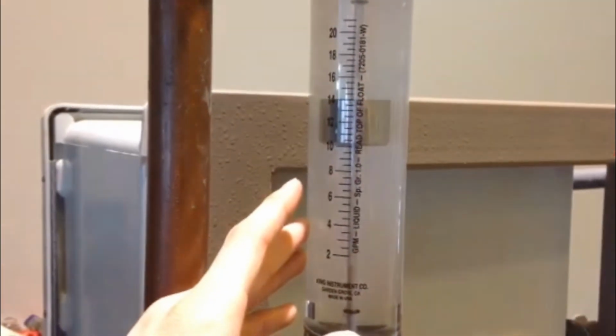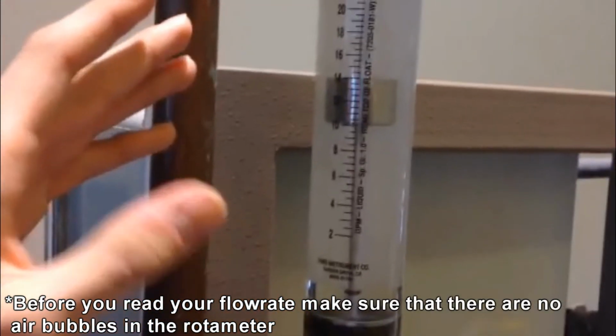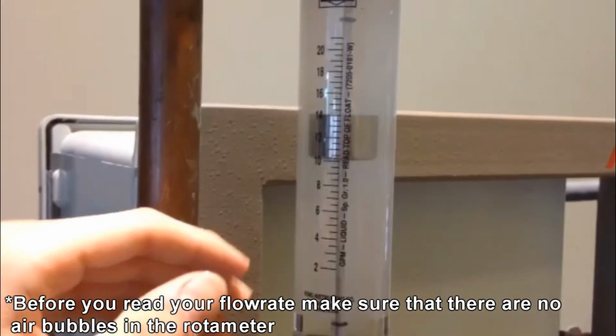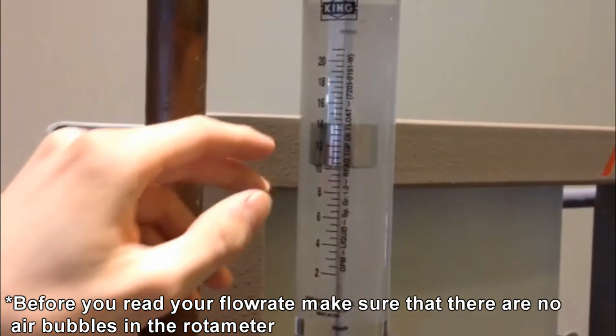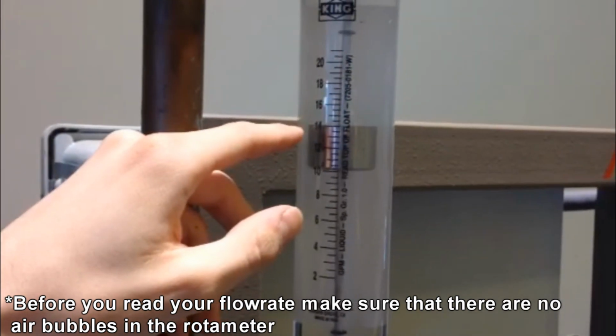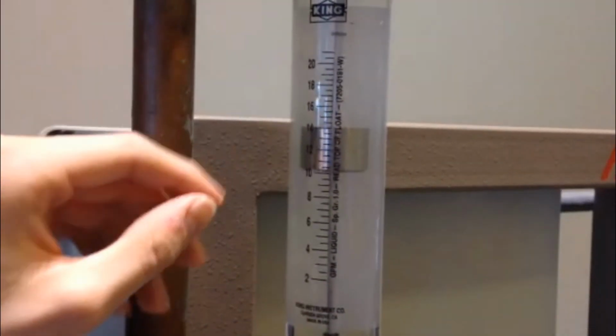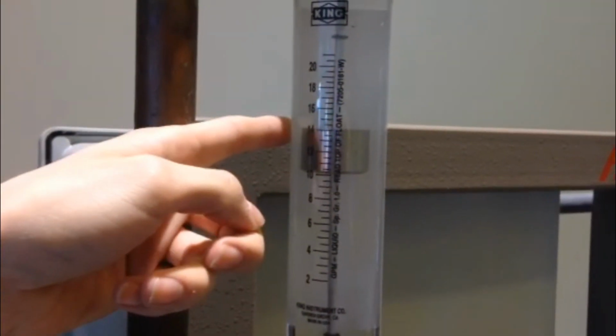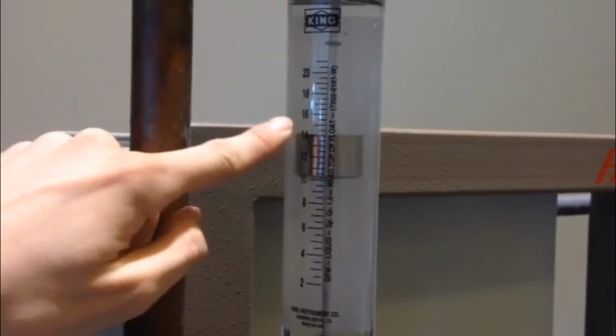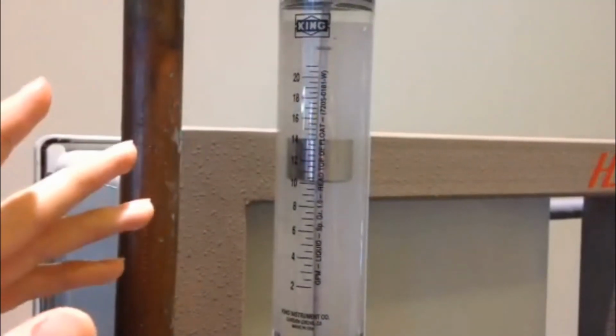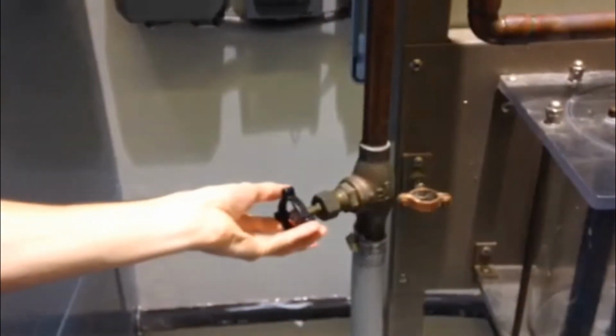So this is a rotameter. It allows us to read our total flow rate. Right now, the rotameter reads that it's about 14 gallons per minute. The way you read this is you look at the top of the float and read it with the corresponding number on the rotameter. Now to change this flow rate, you use this globe valve using the right-hand rule.